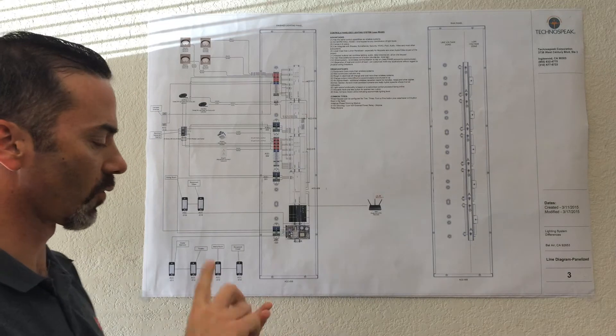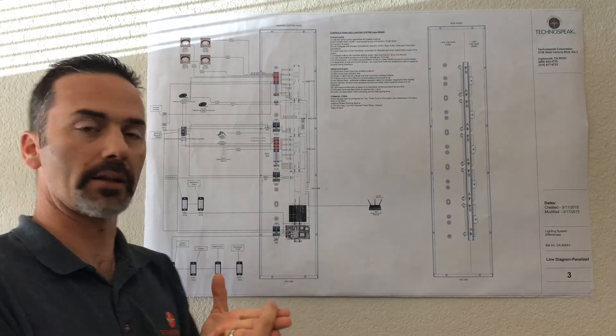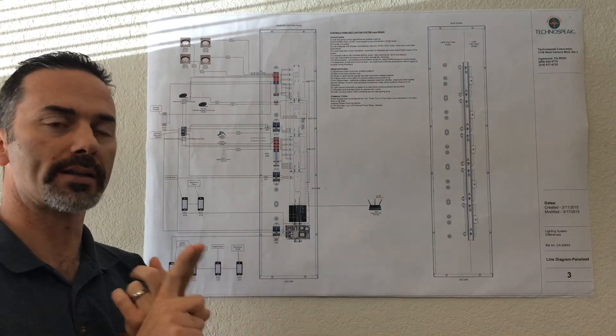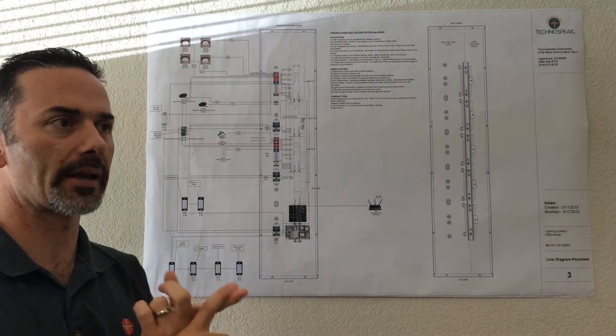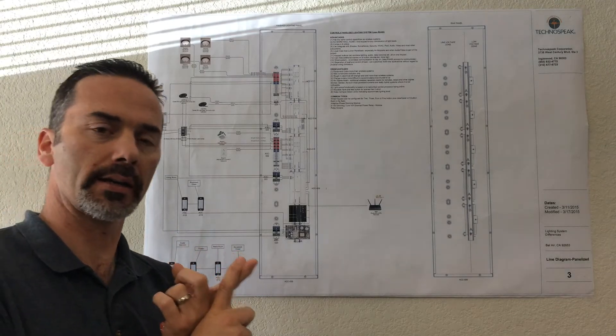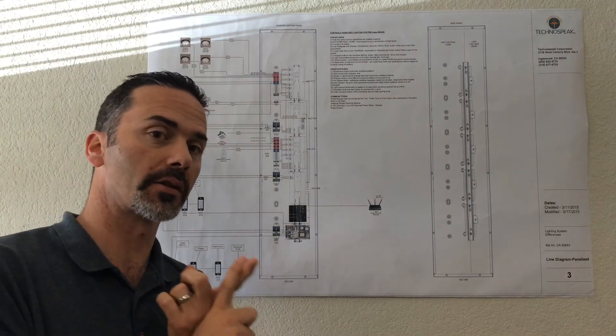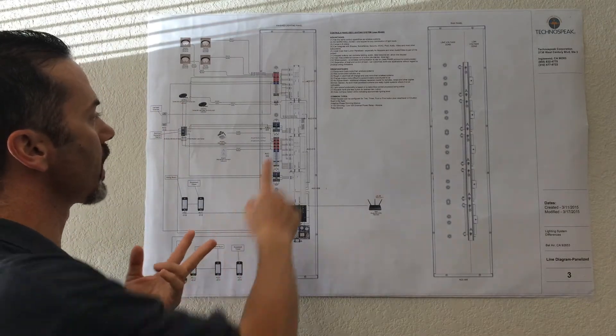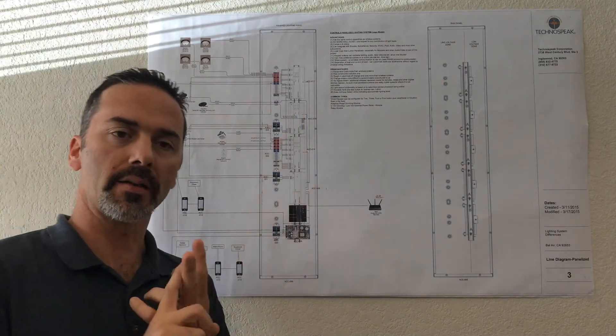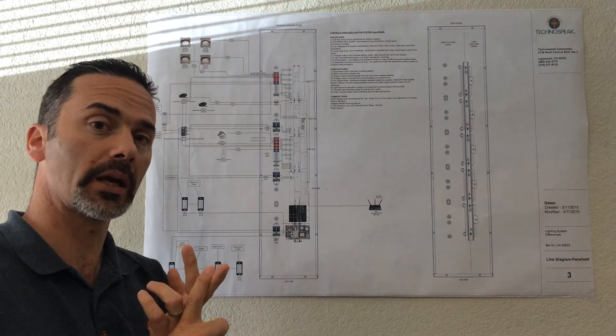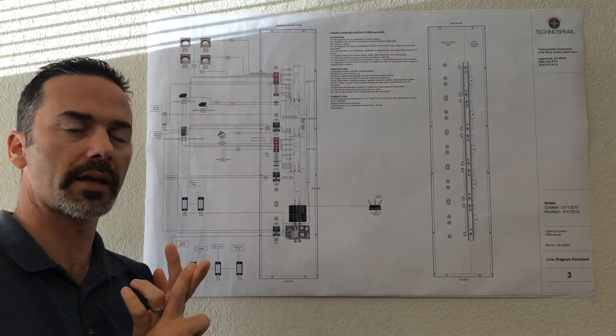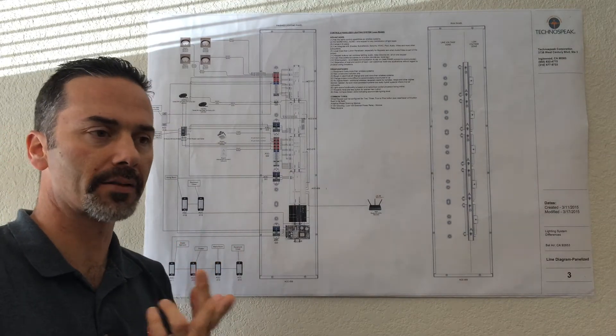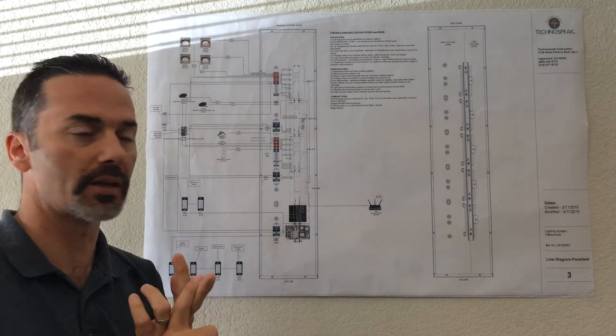So Control4 basically has three lighting modules that they use. One is an adaptive phase module, that's going to handle the bulk of your incandescent and low voltage halogen loads. We have a LED module which does 0-10 volt dimming, and it also can send communication to other dimmable ballasts, dimmable LED ballasts if need be.